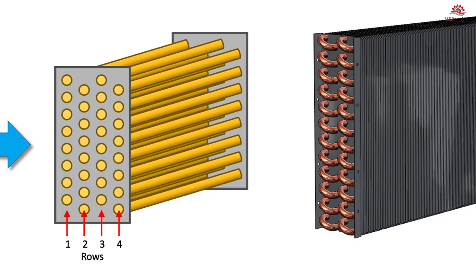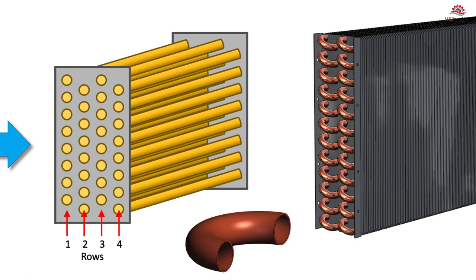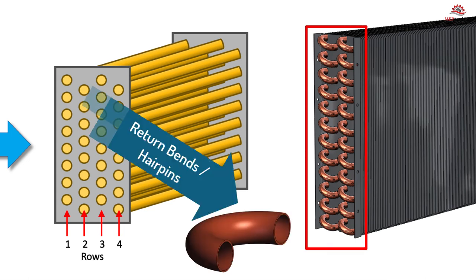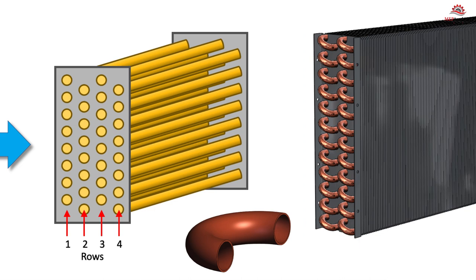To count the rows of coils, there are several methods. First, look at the end of the coil without the header and count the return bends or hairpins. The hairpins are 180-degree fittings that turn the flow back into the coil. Each hairpin accounts for two rows if aligned horizontally. So if you have two hairpin turns horizontally aligned, then you have a four-row coil.